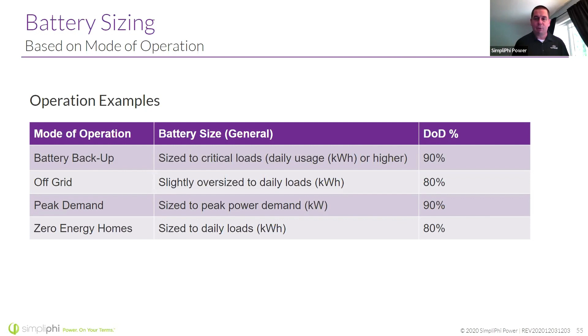When we're sizing our battery, we want to keep that C2 rate in mind. In this example, we've got an Outback 8048, which is an 8,000 watt inverter. If we know that our 3.8 kilowatt hour battery can be discharged at a C2 rate, we know that a single battery can do 1.9 kW. Now, if this inverter can pull 8 kW from our battery bank, we're going to need 5 batteries minimum to be able to provide the power that this inverter can pull. If you undersize the bank and the inverter pulls the whole 8K, you're very likely to damage the batteries and void the warranty. So sizing to a C2 rate is absolutely imperative at the system design phase.